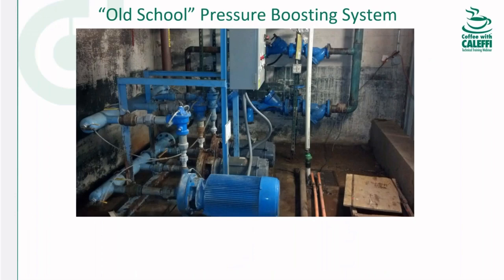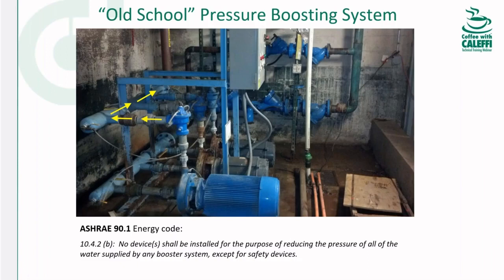Okay, so let's talk about some old school pressure boosting systems. Up until the 90s, booster system pressure was controlled using pressure regulator valves, also called PRVs for short. Here's a multi-pump system. There's a PRV on each pump, and these pumps run at 100% speed, and the PRV is what knocks the pressure down to whatever the set point is. So it's a mechanical control of the pressure. The water comes in the suction line, goes to the pump, gets boosted, more pressure than what we need. Then it goes to the PRV, knocks it down to the set point, and then back out to the building. And nowadays, current energy codes are pretty much eliminating the use of PRVs, certainly to control the pressure. And we'll have a couple of slides on that later on.